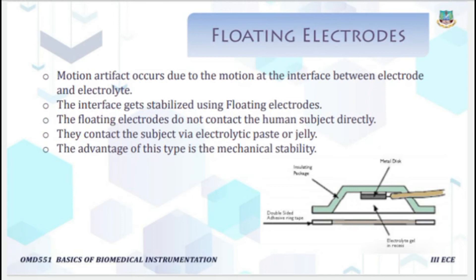The next type is the floating electrode. In this electrode, the metal does not contact the subject directly; contact is made through an electrolyte bridge. By using this, motion artifacts are eliminated. It is also called a liquid junction electrode. The contact with the subject is via an electrolyte paste or jelly, which provides mechanical stability — that is the main advantage. There is no direct contact between the metal disc and the surface of the skin.